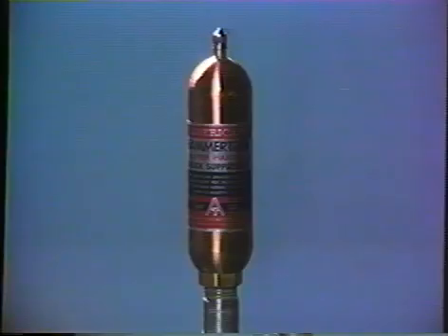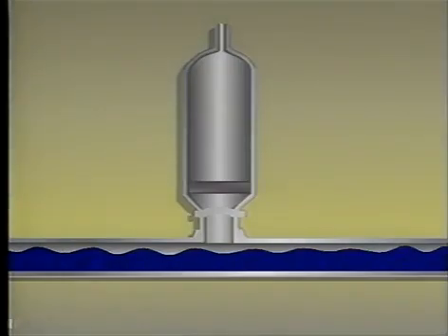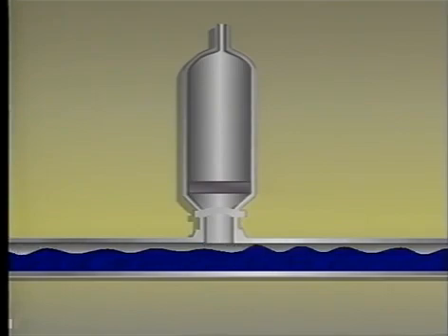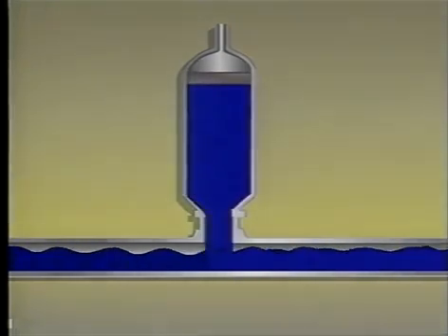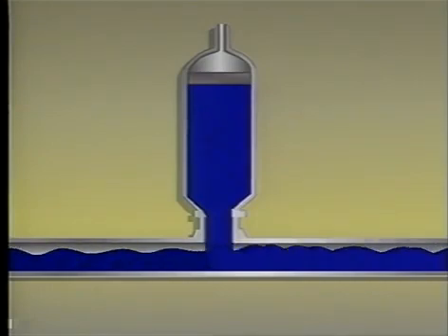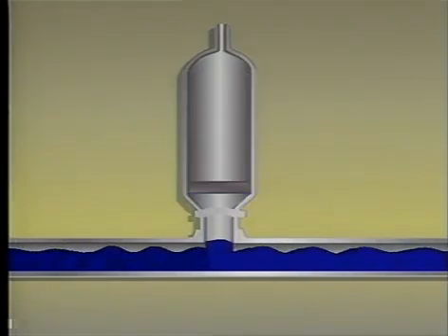Water hammer arrestors, if correctly sized, placed, and maintained, will reduce water hammer. When the forward motion of the water column is stopped by the valve, part of the reversing column is forced into the water hammer arrestor. The water chamber of the arrestor expands at a rate controlled by the pressure chamber, gradually slowing the column and preventing hydraulic shock.